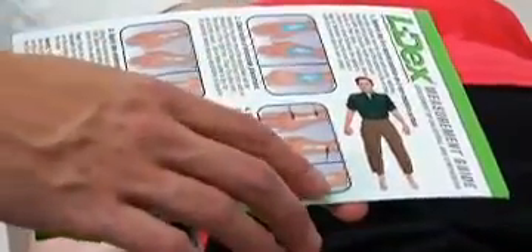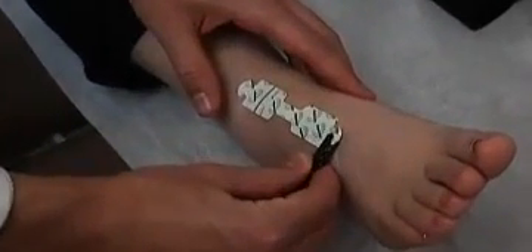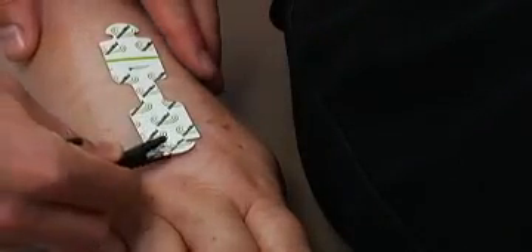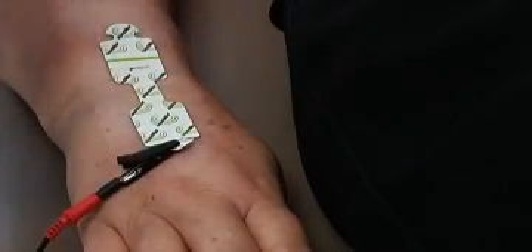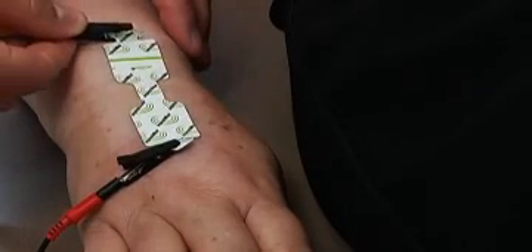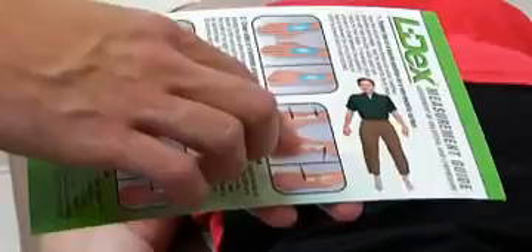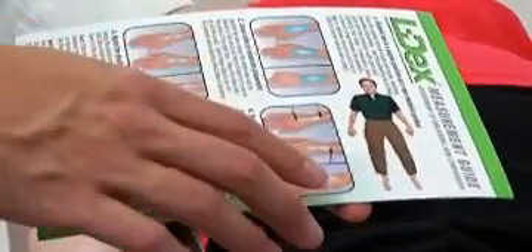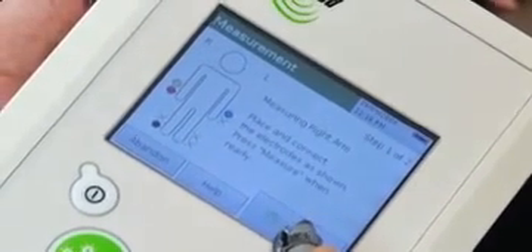Following the provided LDEX measurement guide and the on-screen prompt, attach the color-coded leads to the electrodes on the patient for measurement of the right arm. The black lead will be attached to the distal end of the dual tab electrode on the foot and the blue at the wrist of the left hand. The red lead will be attached to the distal end of the dual tab electrode on the right hand and the yellow at the wrist of the right hand. Double-check your placement with the measurement guide and the on-screen prompt for measurement of the right arm, then press Measure.